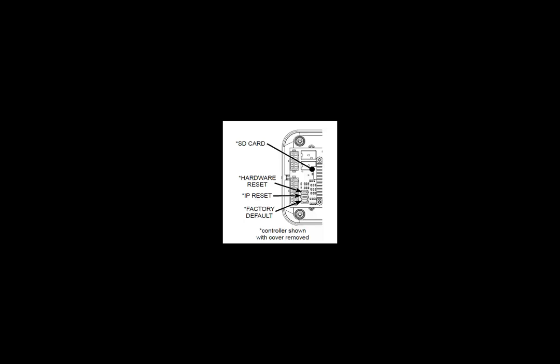Very important! If you are unable to find a controller with the previous methods, each controller contains three reset buttons. One is to perform a hardware reset. The second is to reset the IP address back to the default IP address. And the third is to perform a factory default. If all else fails, it would be recommended to perform an IP reset to set the IP address back to 192.168.0.250. Upon resetting the IP address back to the default address, repeat the steps above.